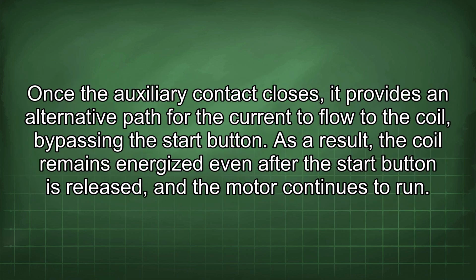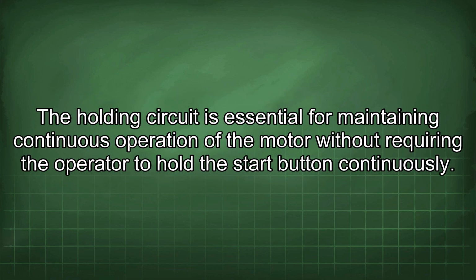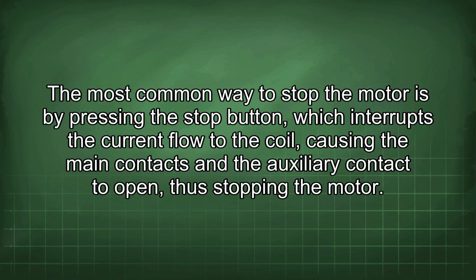Once the auxiliary contact closes, it provides an alternative path for the current to flow to the coil, bypassing the start button. As a result, the coil remains energized even after the start button is released, and the motor continues to run. The holding circuit is essential for maintaining continuous operation of the motor without requiring the operator to hold the start button continuously. The most common way to stop the motor is by pressing the stop button, which interrupts the current flow to the coil, causing the main contacts and the auxiliary contact to open, thus stopping the motor.